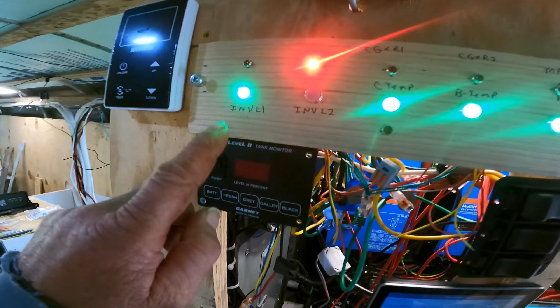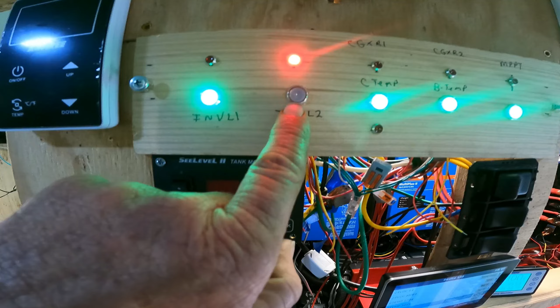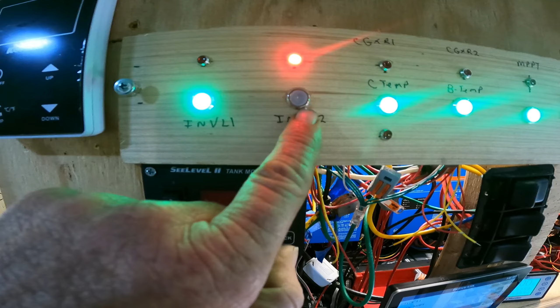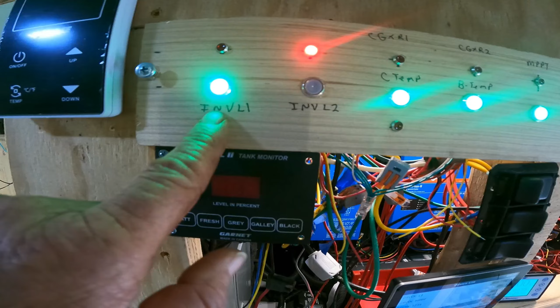The one thing I have to deal with, if you notice right here, inverter on says green, inverter off says red. Realistically, there should not be any power for that red LED to come on. I don't know how that works, I'm going to check that out. However, I'm not going to do that until I get these things configured and make sure it's not a configuration issue. Inverter L1 should be green, and it is green, so hopefully that'll be taken care of. But I'm not sure why the red one is on L2. I'm thinking I may have some wires crossed, and that should be green right now.